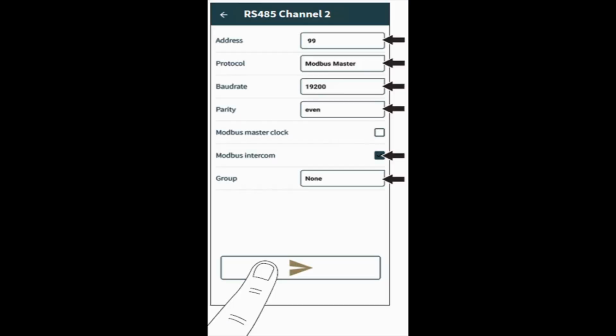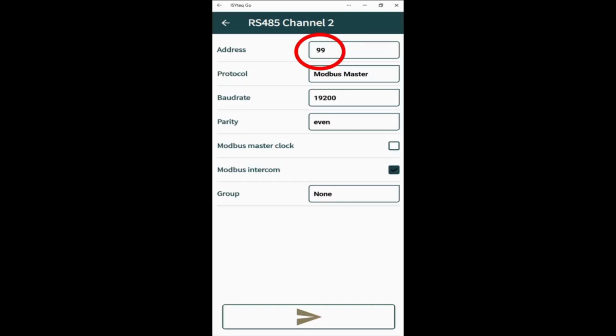You can connect one client and up to 8 server chill beams in a network. A single unit or a client/master unit must have the address 99. All units are delivered with this address, so only the server/slave units need their address changing.